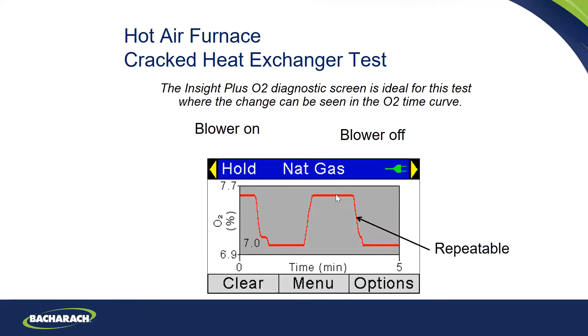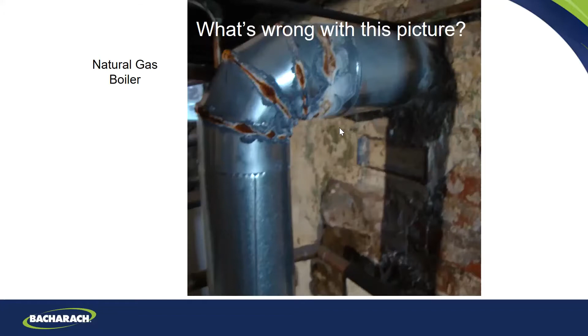One of the questions someone sent in is, what is all this rust and all this white stuff on here? This is like an efflorescence powder, this rust. This really means you're condensing. Okay, you're condensing those flue gases, and we don't want to do that because you're going to get this. So you put your probe in a stack. What do you get? Do you see anything on here? And actually, you can't holler out, so I'm going to holler for you. And someone goes, the stack temperature is too low. Yeah, you're condensing those gases.